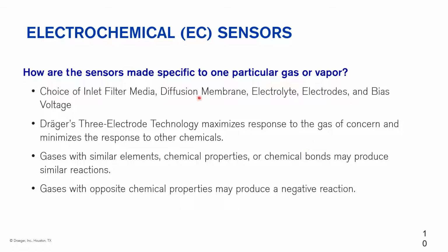So how do we make a sensor specific? That inlet filter media can be, like I said, just a dust mist filter, but it can also be a chemical type filter, such as a charcoal filter. CO sensors generally will have a charcoal filter on the inlet of them, so that they will scrub out H2S. With no filter, a CO sensor would respond better to H2S than it does to CO. The diffusion membrane, we can vary the pore size on that membrane to also control what gases actually get into the sensor. The electrolyte, we can vary the composition of the electrolyte to help pinpoint the gas that we're trying to detect. The electrodes in the sensor are made of precious metals. We can vary the composition of the metals to also control what reactions we get.